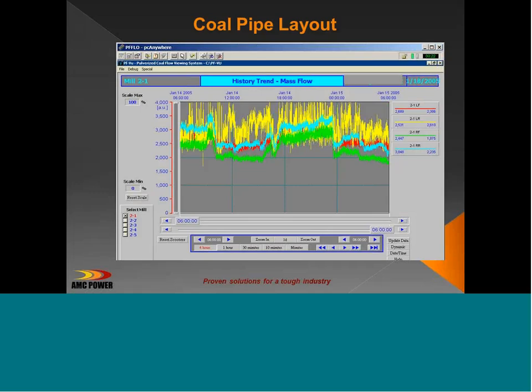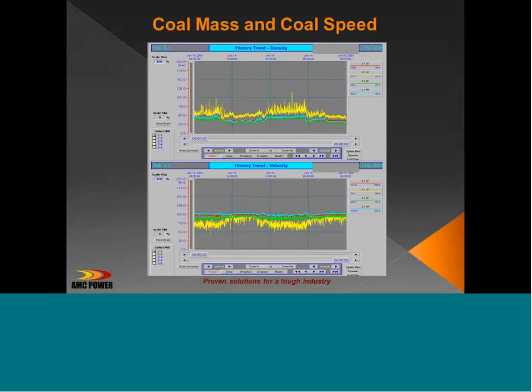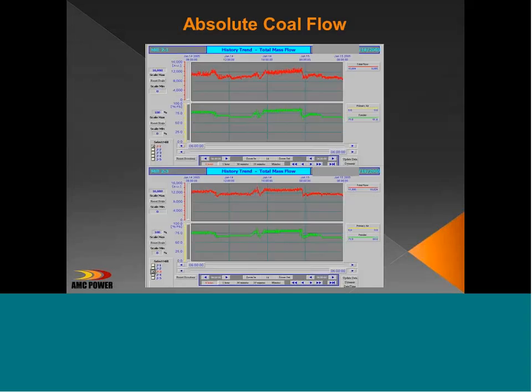When we talk about the accuracy of the device, we're measuring coal mass flow in real time, every second. So if we sum the 4 pipes of this pulverizer over this 24-hour period, the top screen is the sum, the bottom screen is the gravimetric feeder. Basically every blip that feeder goes through, you're going to sense with the coal flow signals. So the accuracy is certain.